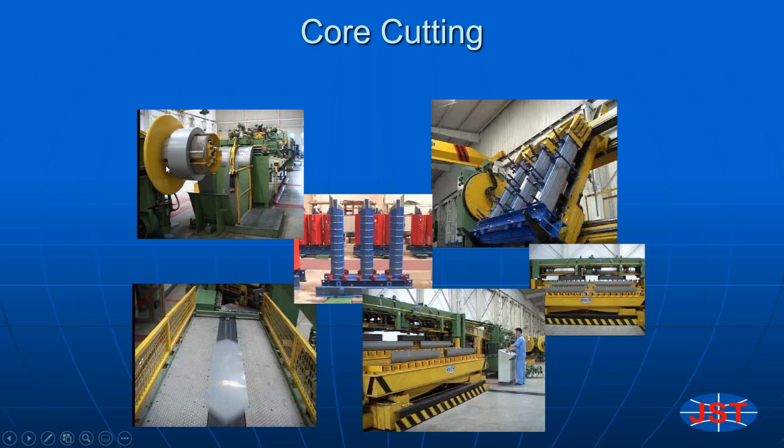And here you see we have a turret, and there's multiple turrets with different widths, and they will cut the laminates. Now, the other thing we need to do is, because they're miter joints, we need to step lap it, so it's step lapped and mitered to really reduce the noise that you would get, and that's actually audible noise. So what the machine does, and it's all computer controlled, it will select a certain width, and then it will cut off a series of laminates, each one a little bit shorter, and then it starts all over again until you're done with that width, and then it switches to the next width and starts over again.